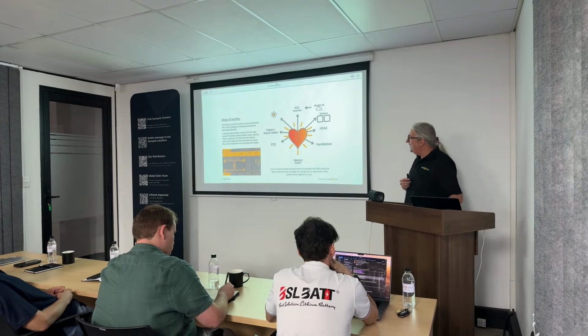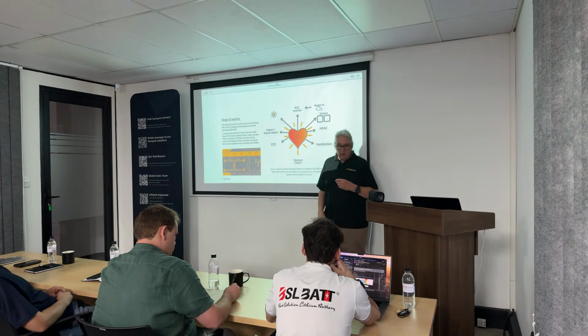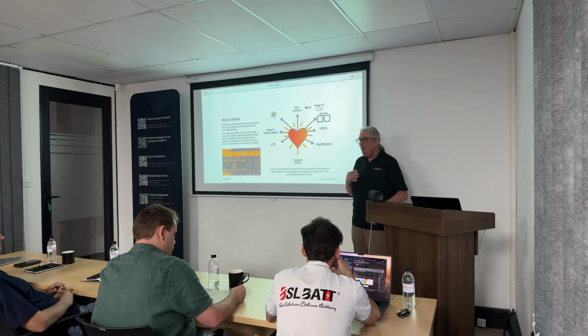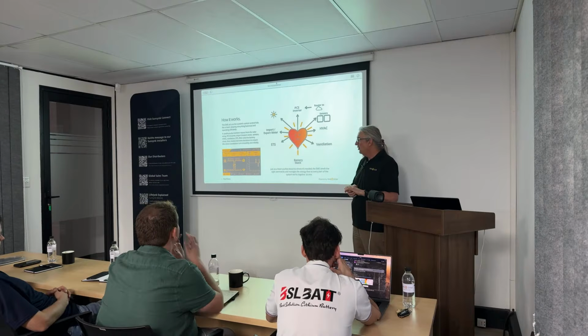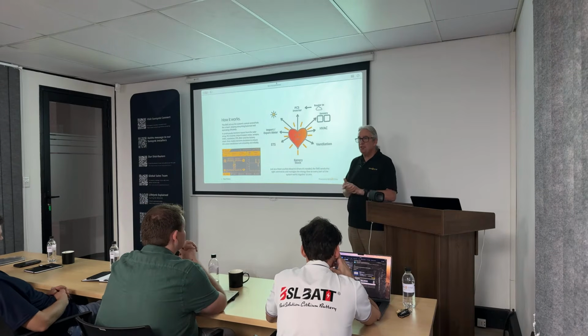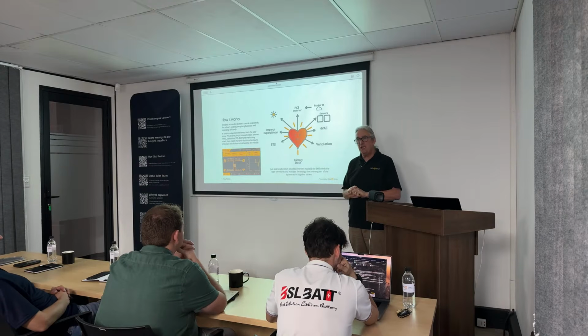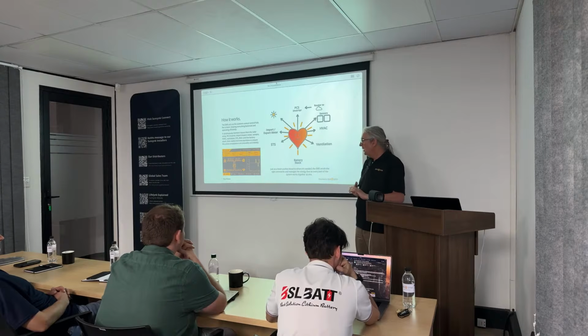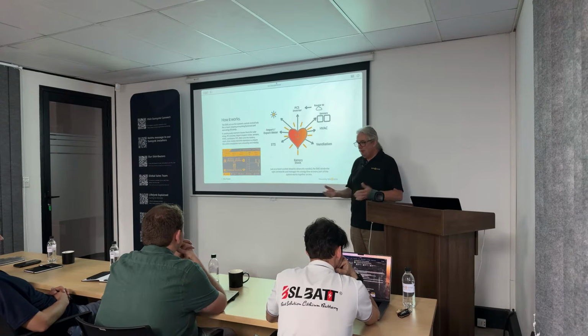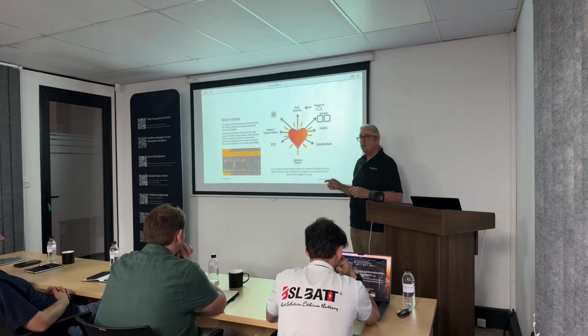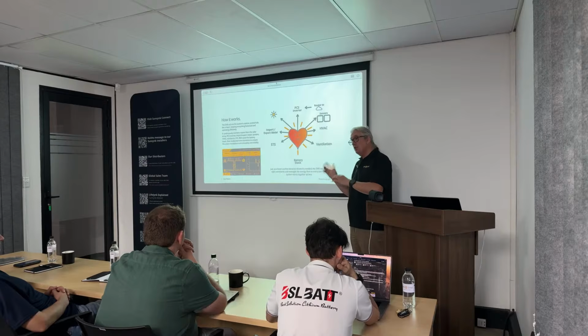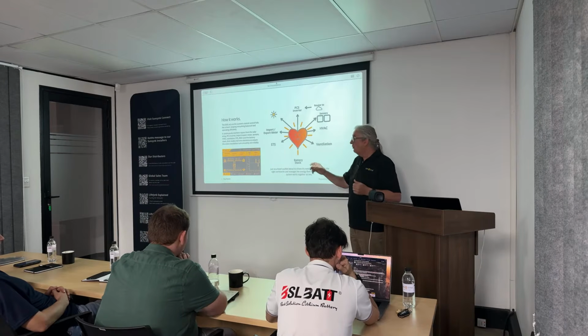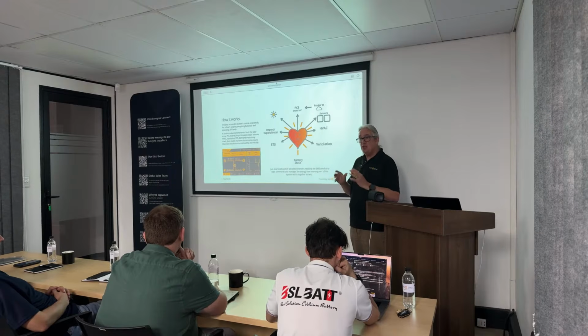The heart of it is the EMS. This is the EMS, the energy management system. I'll put this microphone in so we record it. Lots of people make, and there are quite a few, various modular systems. But a modular system, when you've got a PCS or an STS or an MPPT in its bare-bones modular form, is probably not much use because it's dumb. It doesn't have a screen on it. It has to be controlled by something. And so the EMS will bring the whole lot together, as if it's a hybrid inverter. It can tell when to charge or discharge, it can control the voltage, everything is controlled by the EMS. So you have a local EMS that actually controls everything.